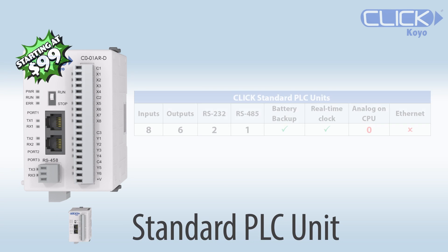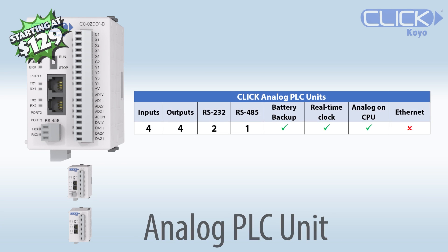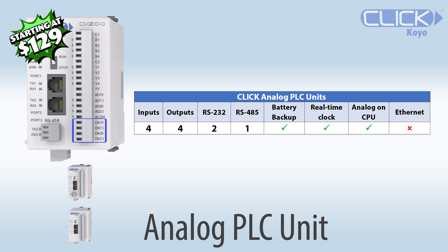Next is the Standard Models, which adds battery backup that also provides a real-time clock for programming. This unit also adds an additional RS-485 port, giving you a total of 3 independent serial ports. Next, there are the Analog PLCs that have 4 discrete inputs, 4 discrete outputs, 2 analog inputs, and 2 analog outputs. These units also have a battery backup and real-time clock with the 3 serial ports.